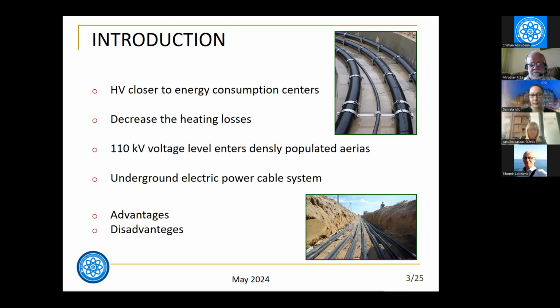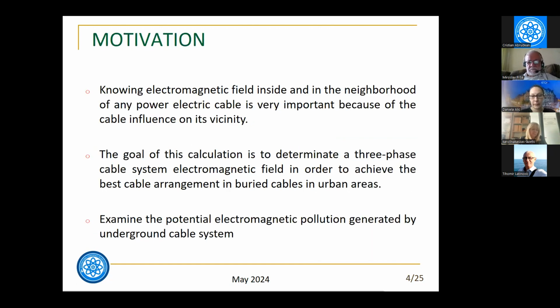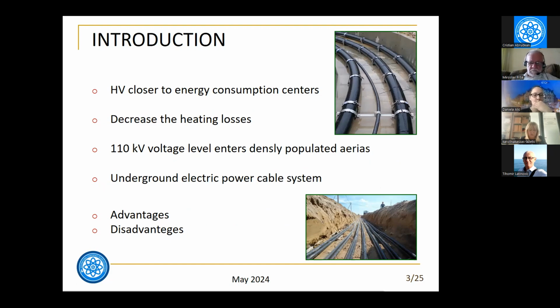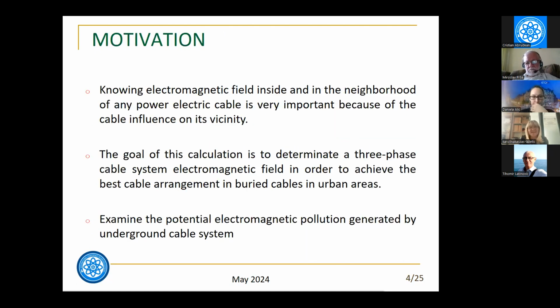Underground electric power cable systems are resistant to environmental damage, to rain, snow, wind, ice, etc., and have reduced space requirements. Moreover, due to their shielding systems, high-voltage power cables have greatly reduced electromagnetic field emission. Besides that, applying buried cable systems, the security and reliability of electrical energy transmission are significantly increased, which is very important for the consumers. The disadvantages of underground cable systems are that they heat up significantly, which leads to degradation of the insulation, and their high price.